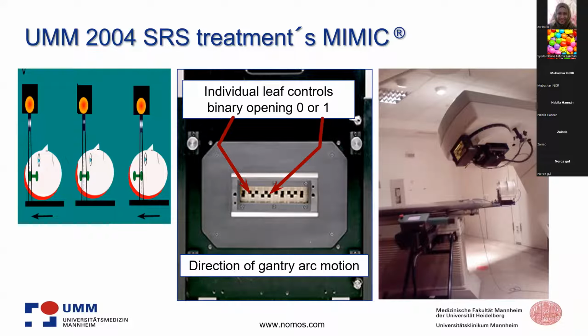So in 2004, we introduced the MIMiC from the Nomos company. This was an add-on device. You see here. This was attached to the machine's head, and you have individual leaf controls, and you have 0 or 1. That means you have a very deep modulation, because you have the maximum. This is the maximum grade of modulation used by this type of modulator.